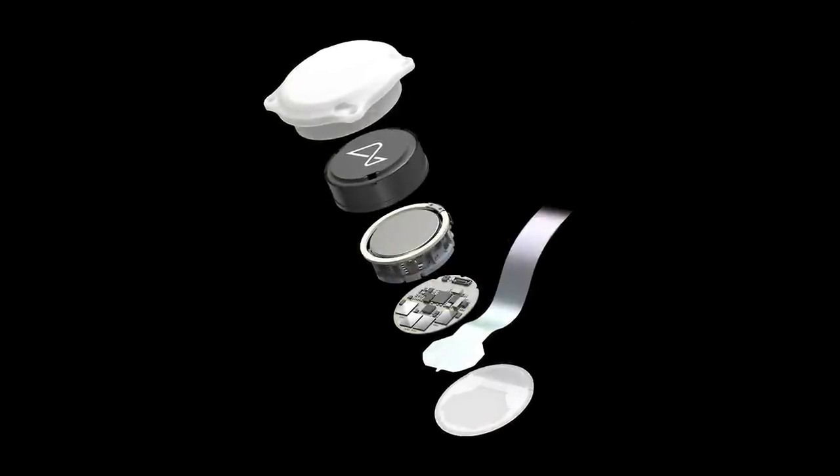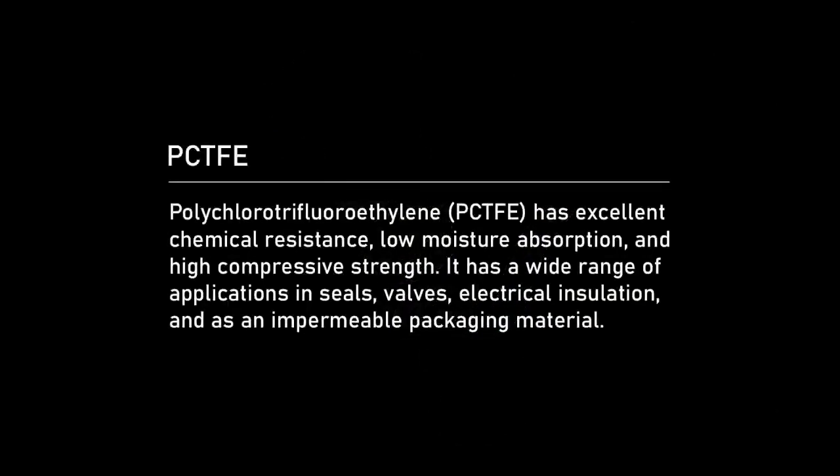Yeah. No. All right. But by the way, the other thing that also is interesting about our enclosure is, if you look at our implant, it's not your common-looking medical implant that usually is encased in a titanium can that's laser welded. We use this polymer called PCTFE, polychlorotrifluoroethylene, which is commonly used in blister packs. So when you have a pill and you're trying to pop the pill, there's that plastic membrane. That's what this is. No one's actually ever used this except us. The reason we wanted to do this is because it's electromagnetically transparent. So when we talked about electromagnetic inductive charging, with a titanium can, usually if you want to do something like that, you have to have a sapphire window, and it's a very tough process to scale. So you're doing a lot of iteration here on every aspect of this: the materials, the software, the hardware, the whole shebang.